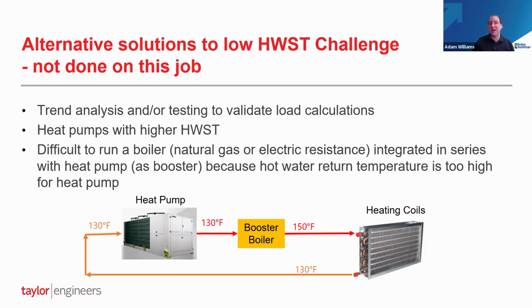Other thing you can do, kind of like Kyle mentioned, is testing, where you can say, well, hey, on this early morning, try lowering your hot water temperature. The problem with that is, if you're planning on replacing the coils anyway, you do that test and people say, well, it was uncomfortable. And you're like, well, we're going to replace that equipment, so you should trust us, right? That can sometimes not work out very well if you're already planning on changing the system.